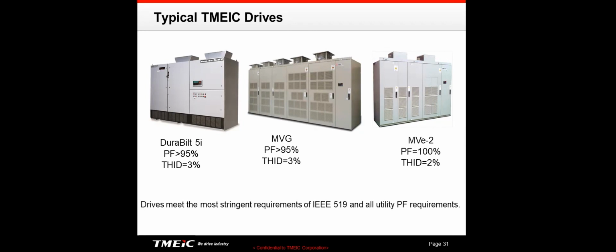Now, typically, I used to say, oh, you get over 95% power factor, you're good, don't worry about it. And there's still something to be said for that. But think about it, if you have 100% power factor, you're actually powering your load on 5% less current than if you have a 95% power factor. So when you get into very large drives, there is something to be said for 100% power factor. And that drive will actually control the power factor so that it's 100% at basically all speeds and loads. And your total harmonic distortion is approximately 2%.